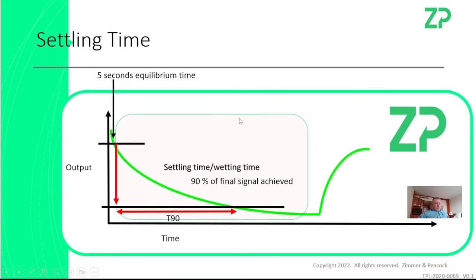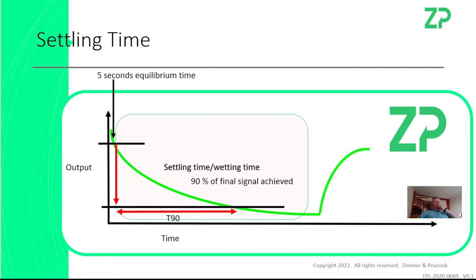So settling time — what do we mean by it? When we first turn on a sensor, a good example is a continuous glucose monitor (CGM), and the signal can start high. It can take some time for the signal to essentially reach baseline. The settling time for me is the time it takes for the apparent signal to get within 10% of the baseline. Otherwise you could wait forever to really reach baseline. You can call it T90 — a term quite well used in engineering — the time you get within 90% of a final outcome. The classic example is continuous glucose monitoring: when a sensor is first used it has to wet up, and it can take some time.